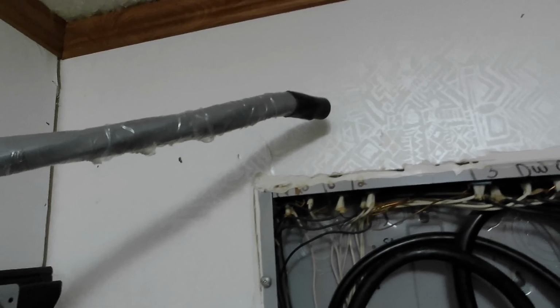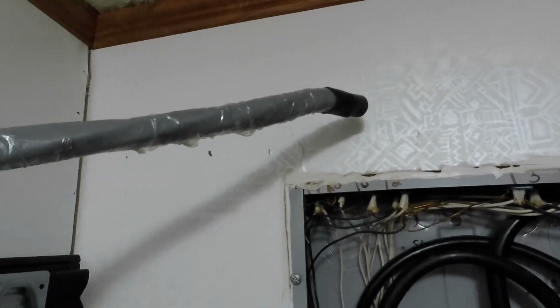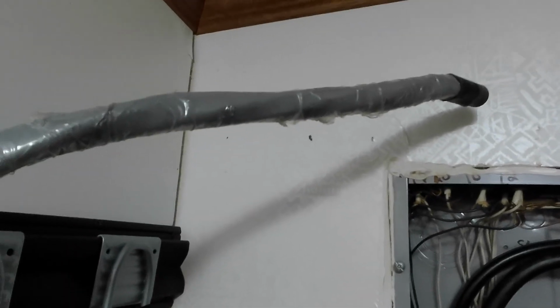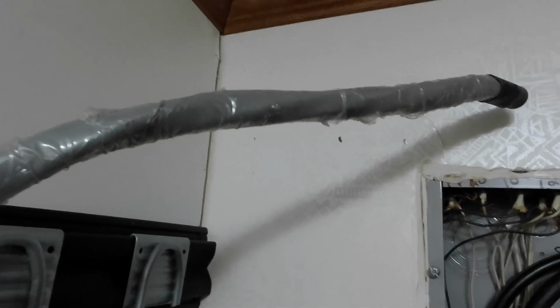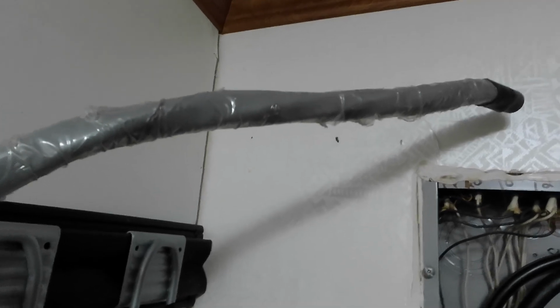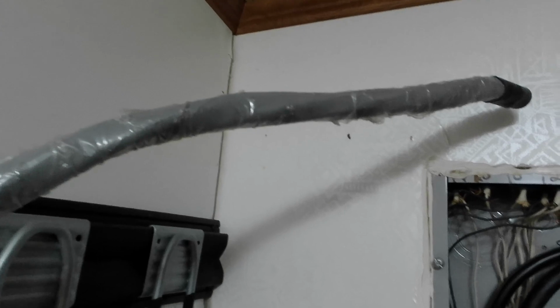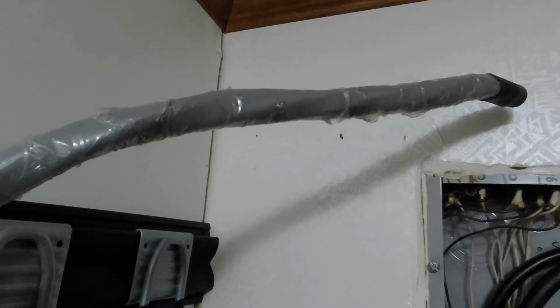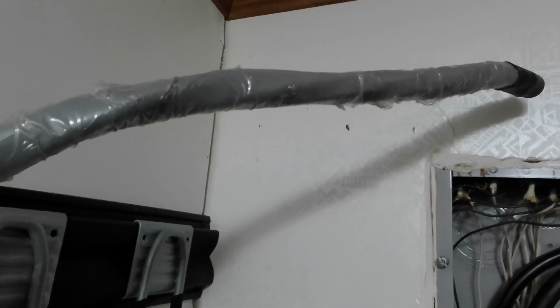This is a number 2, not 2-aught, but a number 2 AWG aluminum service entrance cable. So it's 3 number 2 aluminum wires and a number 4 aluminum wire for the ground. So you got 2 hots, a neutral, and a ground in here. And this will carry up to 100 amps on it.